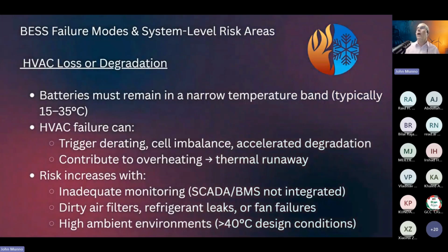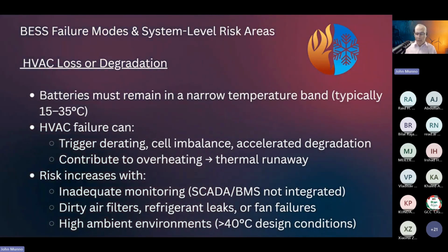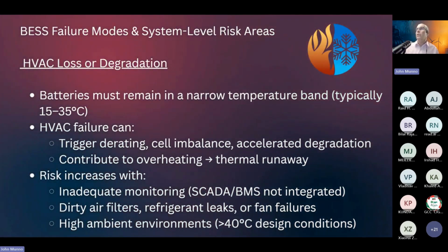We can have HVAC loss or degradation. And what happens there is that our batteries can overheat. This is just something that we can monitor before we get into the batteries going into thermal runaway. So it helps if our monitoring includes the HVAC. And if we don't have good monitoring of the HVAC, then we may just be relying on the BMS, and so we're just waiting for the failure to happen.